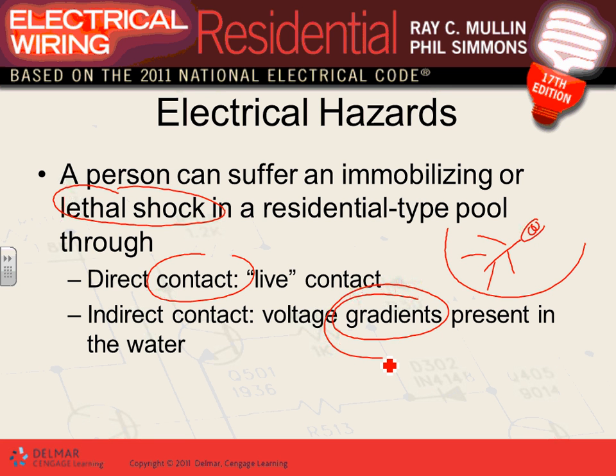So that's why it's the perfect shock. The perfect shock is: here you are, grabbing on something energized, barefoot on wet ground that's saturated with water. What better perfect shock is there than that? Do you see the gravity of why it's a big deal? So in order to minimize you grabbing on something energized, the code requires you to remove all energized things. You don't put anything energized closer than 6 feet from the inside walls of a swimming pool. So you can't be in the swimming pool and reach out 6 feet.